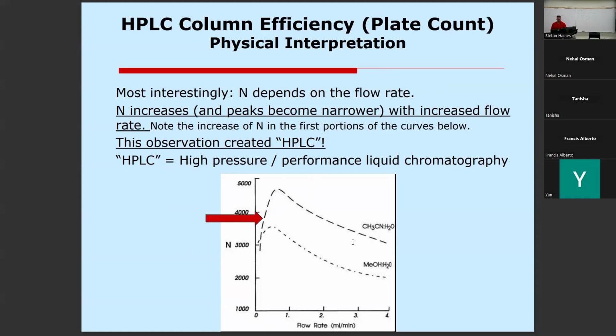So you have to know the parameters your column can take, right? They can take a certain amount of PSI, but then you'll start noticing you get leakage and stuff like that. So I know one time at Centennial College, the system wasn't working. We looked inside the machine, it was dripping all over the place. We didn't know why. Turned out someone had added a 0 to the milliliters per minute. So instead of being like 10 milliliters per minute, someone had set it to 100 milliliters per minute. And that's why the column wasn't able to handle it, because you're trying to force so much through this tiny little metal rod, right? Trying to force 100 milliliters per minute, it just wasn't working, right? So it was spraying everywhere.